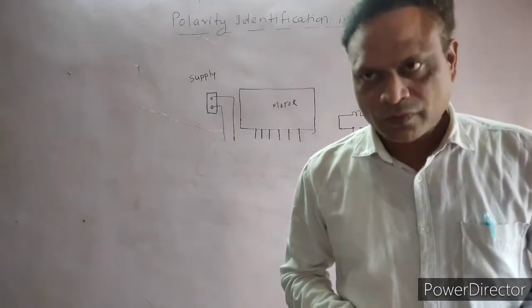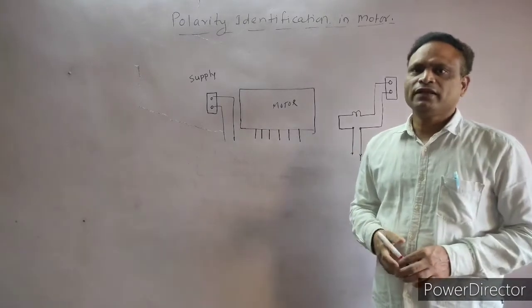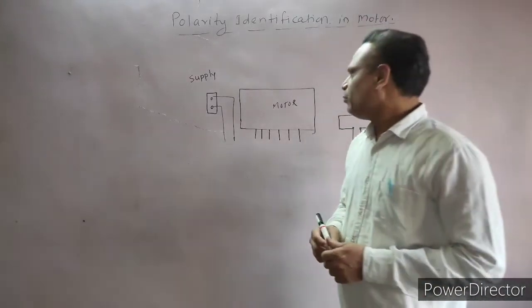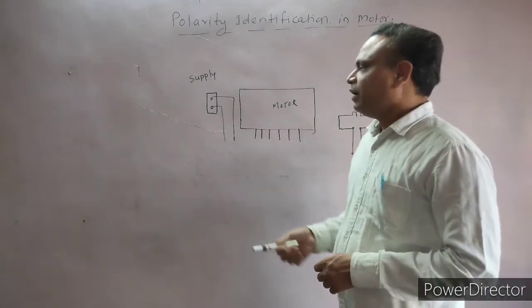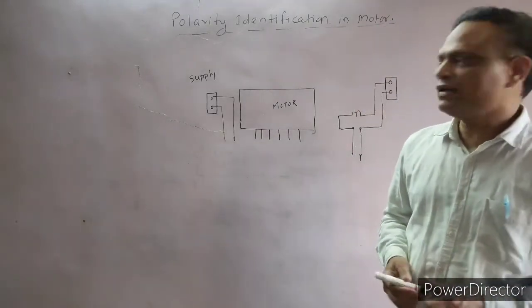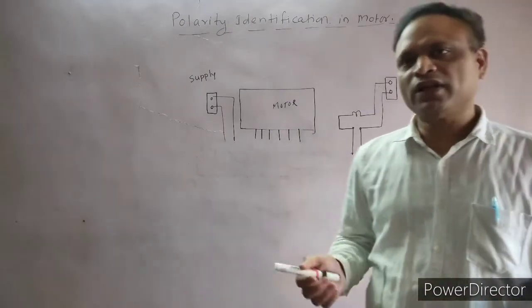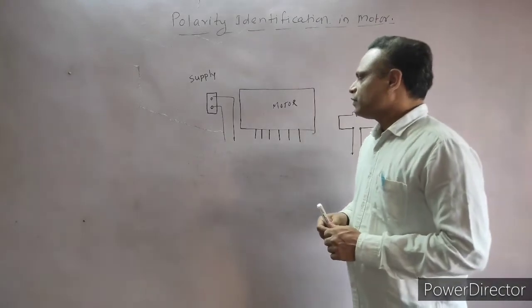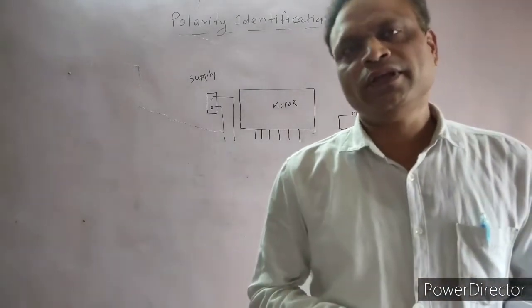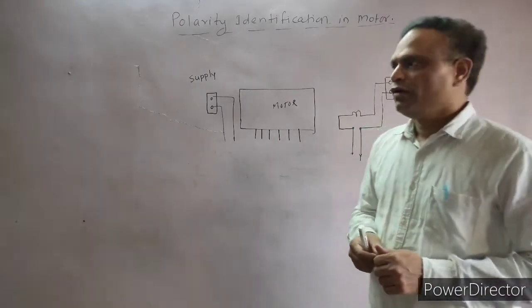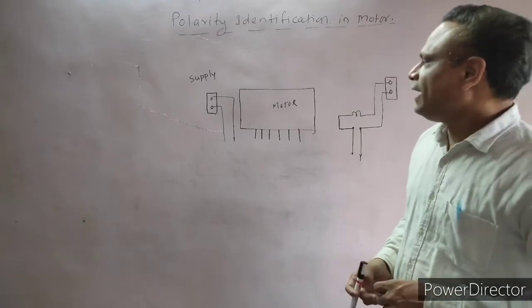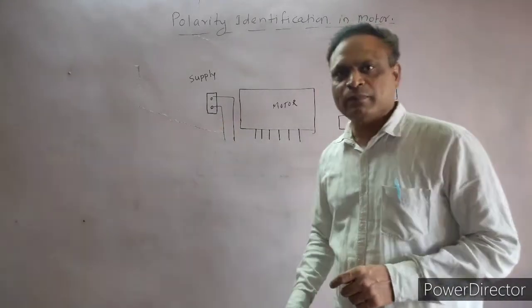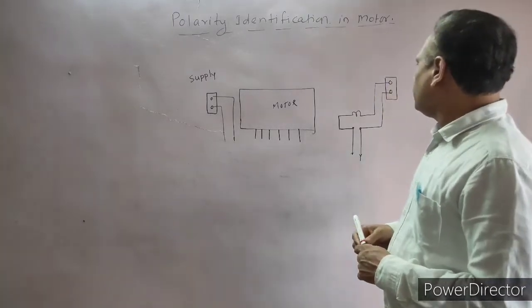Welcome to AS Educational Channel. Today we will see the method of finding the unknown polarity of coils from a motor. We have six wires coming out from the motor. The motor is star connected and we don't know which terminals belong to which coil. To find out, we will use a series lamp, and for identification of polarity, we will use a power supply.